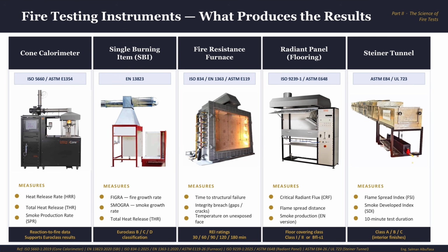And it looks like this: a 7.6 meter enclosed horizontal tunnel. The specimen is mounted face down on the device, and then the control flame ignites it from one end to the other. And you have windows here so you can visually inspect the test. The smoke density is also measured here. And the test runs for exactly 10 minutes. Exactly 10. Any interference invalidates the entire result.